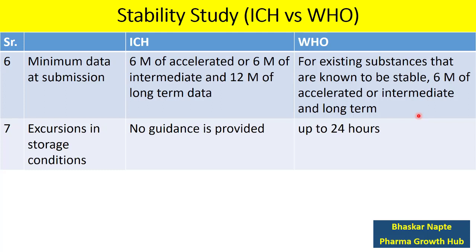Regarding excursion in storage condition — in case your stability chamber is out of order for some reason, how long can it be out of order? ICH provides no such guidance. However, WHO says up to 24 hours. Within 24 hours, you need to take corrective measures and ensure your stability chamber is functioning as expected, or transfer your samples into another suitable chamber with the same or similar condition.